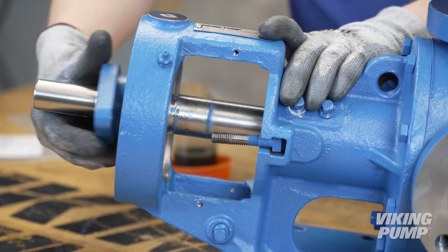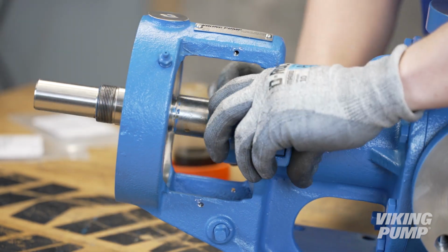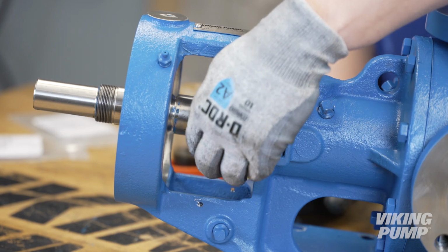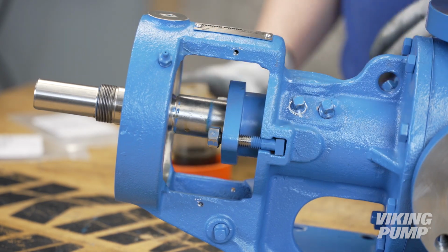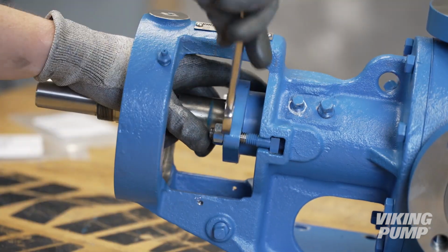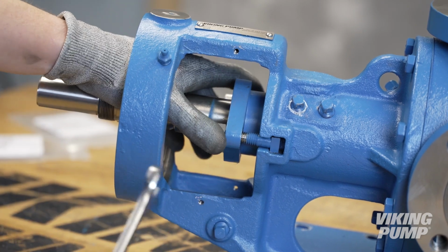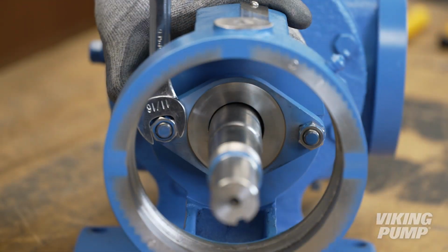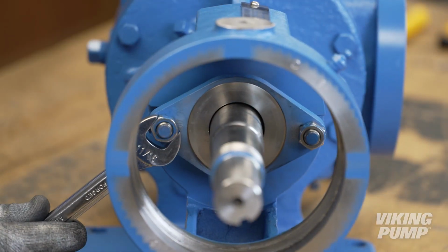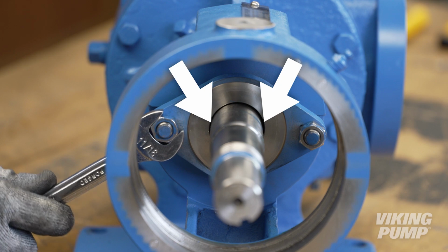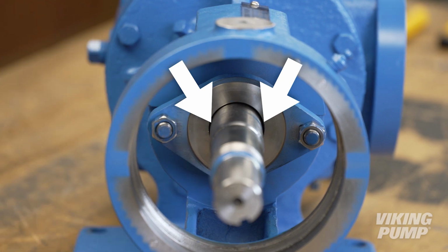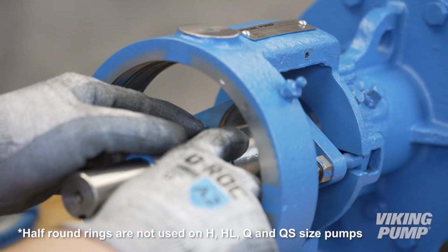Install the packing gland. Install the lock nuts. Tighten the nuts evenly until the packing gland is snug against the packing. Alternate tightening the nuts and ensure that the gland is evenly spaced to the left and right of the shaft. Do not over-tighten. Install the half-round rings.